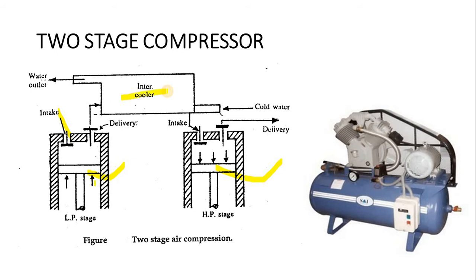What is exactly the intercooler? This is the main interesting question. The main function of the intercooler is to keep that particular pressure constant and reduce the temperature. It is necessary to reduce the temperature because high temperature air when it enters the second stage affects the performance as well as the seals, and there are chances of lubrication swelling. The intercooler is just one kind of heat exchanger. Sometimes water is continuously circulated through that area, and sometimes air-cooled fins are used for better heat transfer.